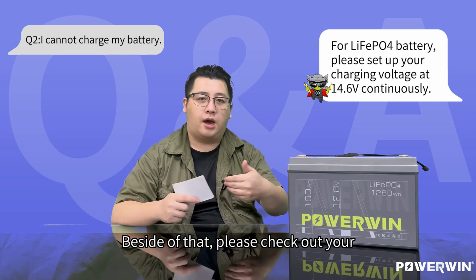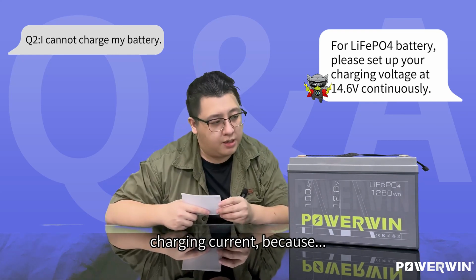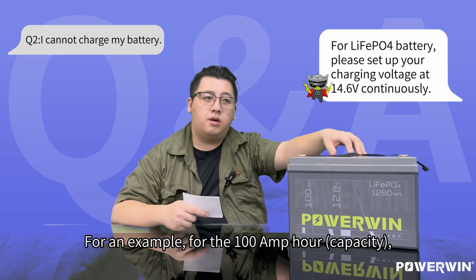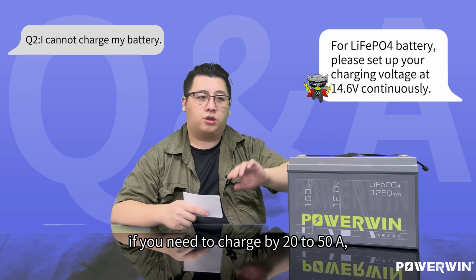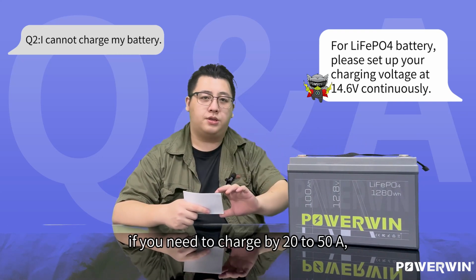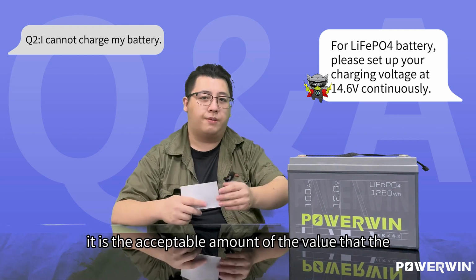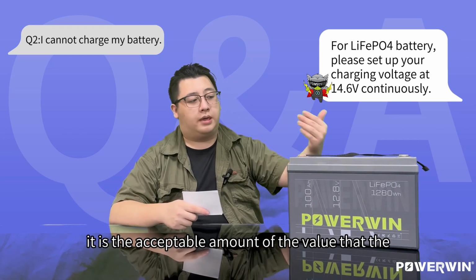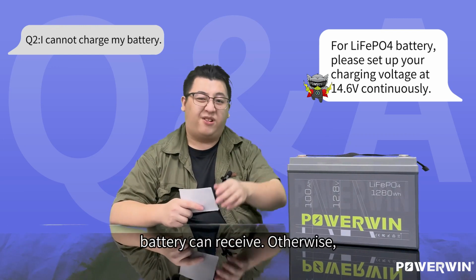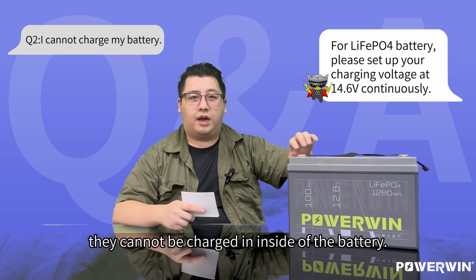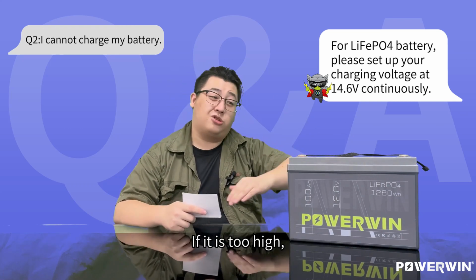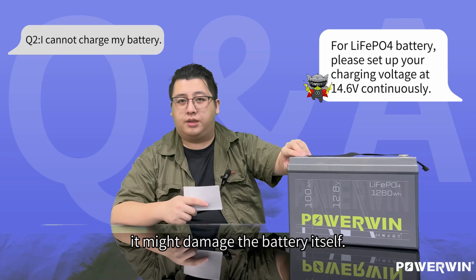Besides that, check the charging current. For example, for a 100 amp-hour battery, charging at 20 to 50 amps is an acceptable value the battery can receive. If the amperage is too low, it can't charge the battery properly; if it's too high, it might damage the battery.